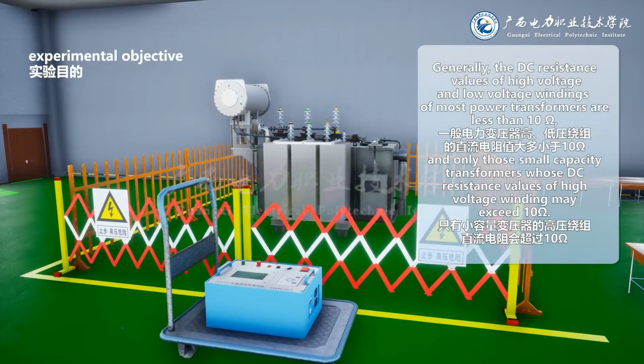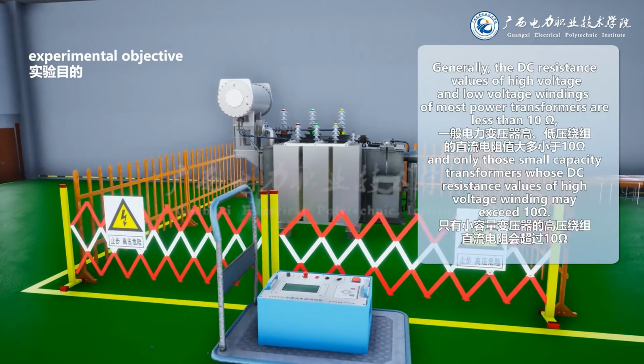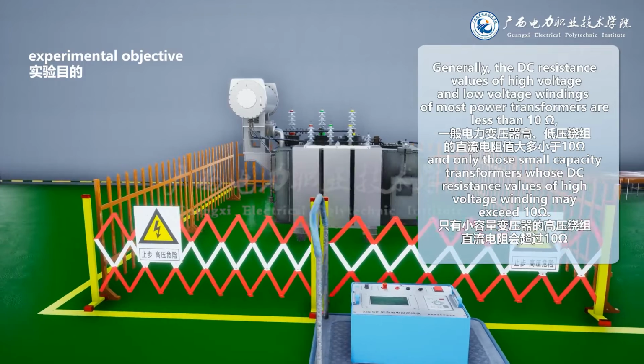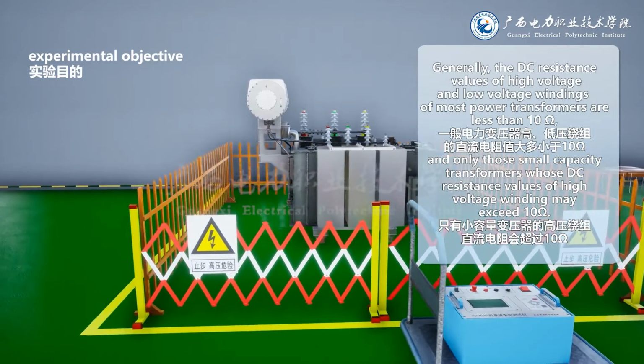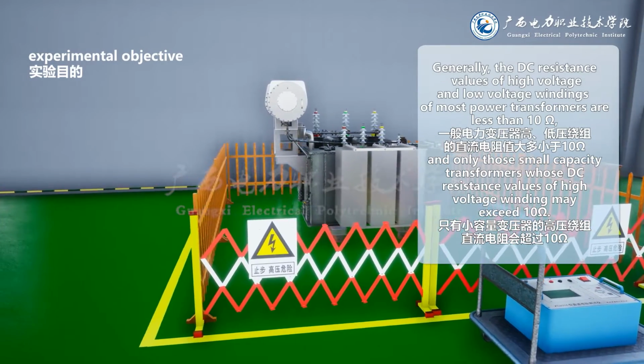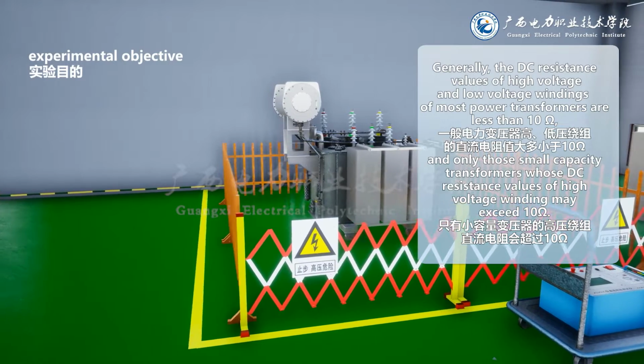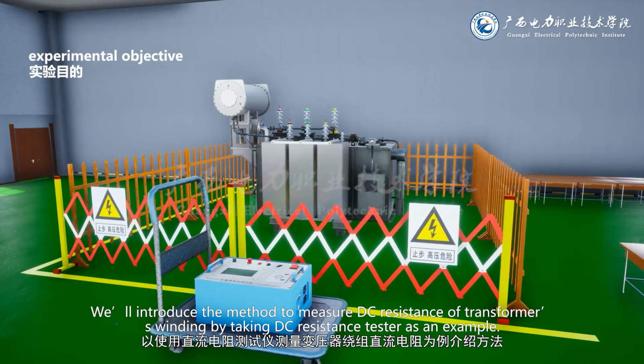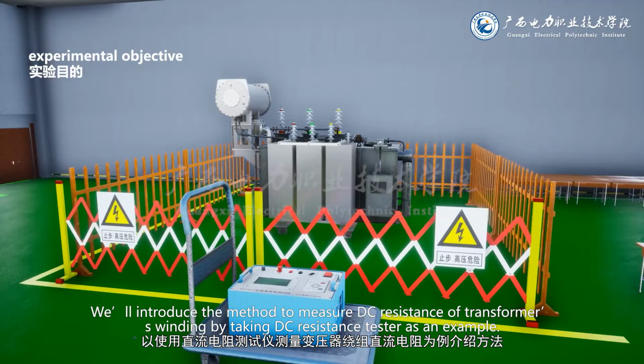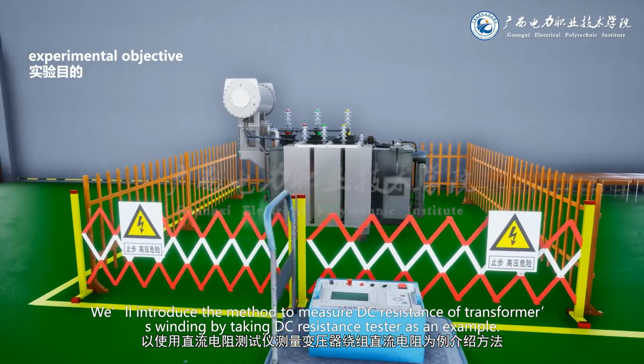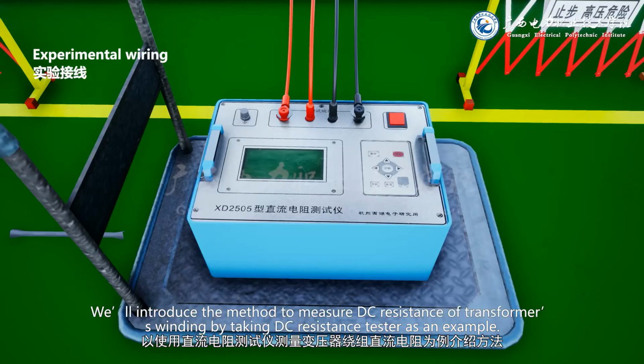Generally, the DC resistance values of high voltage and low voltage windings of most power transformers are less than 10 ohms, and only those small capacity transformers whose DC resistance values of high voltage winding may exceed 10 ohms. We'll introduce the method to measure DC resistance of transformers winding by taking DC resistance tester as an example.